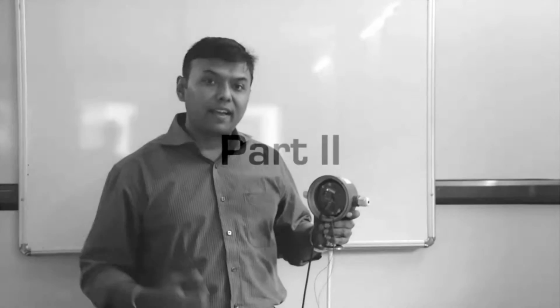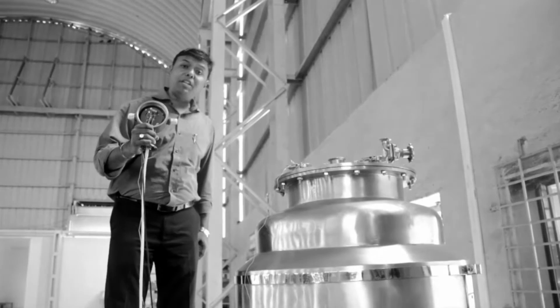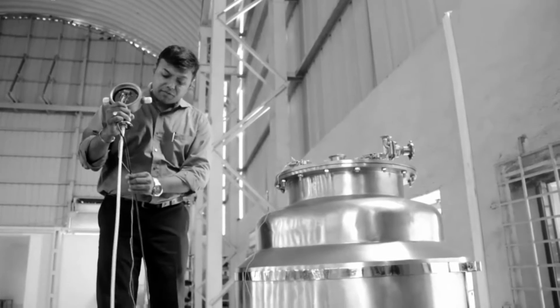Now let's move on to the part 2 of the calibration, where we will have to do this calibration on a tank. Here we are going to do a span calibration. That is, we need a 4 milliampere when your tank is absolutely empty, and a 20 milliampere when your tank is absolutely full. So for this, we shall show you the calibration on the tank. This is the part 2 of the calibration process of the capacitance level transmitter.